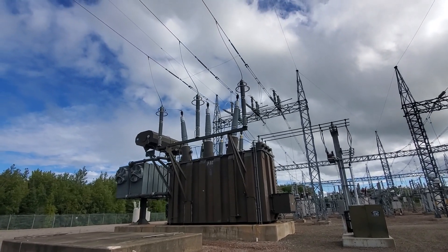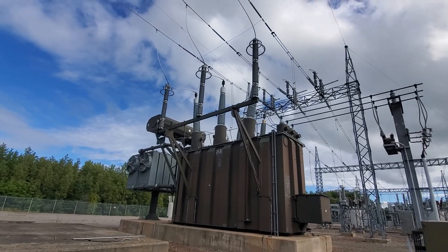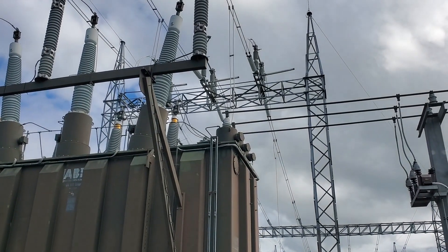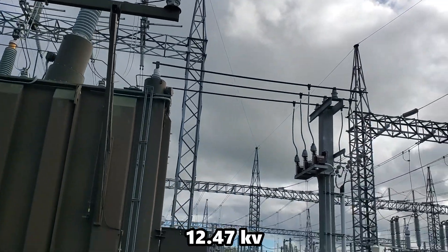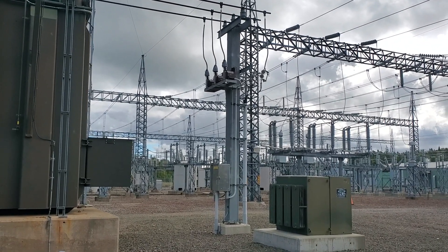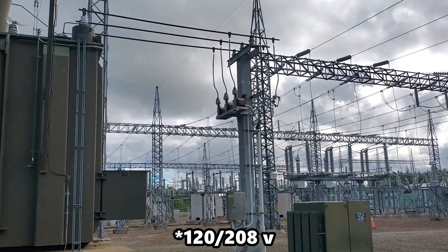So we've got 230KV feeding this power transformer, and it's got a little tap off. You can see the three bushings on the right hand side, which transfers that down to 12.47kV across that buswork and into this little pad mount transformer, which then again steps that down to 120, 240 volts.